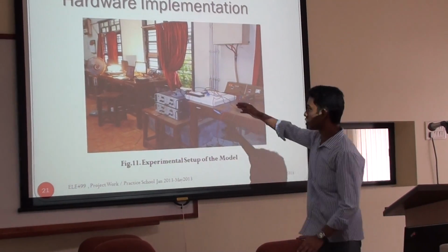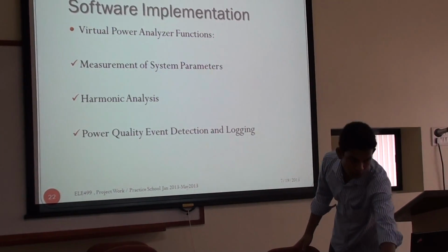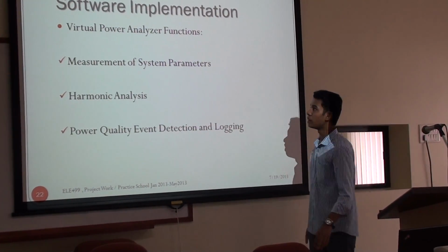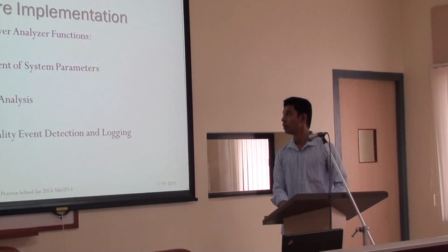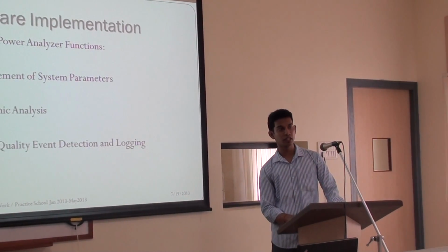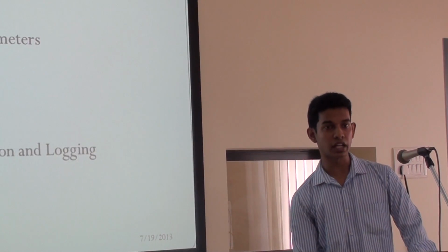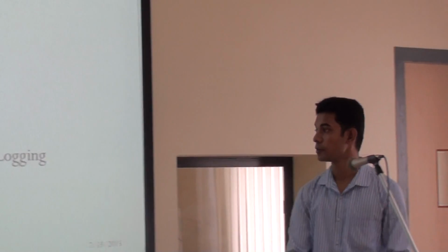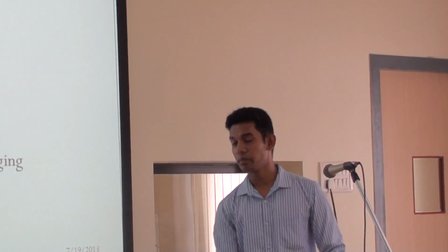This is the screenshot of the setup. Software implementation. So what functions does the virtual power analyzer developed by us provide? We can measure different system parameters. By system parameters I mean voltage, current, power factor, active power, reactive power, harmonics, and power quality event detection and data logging.